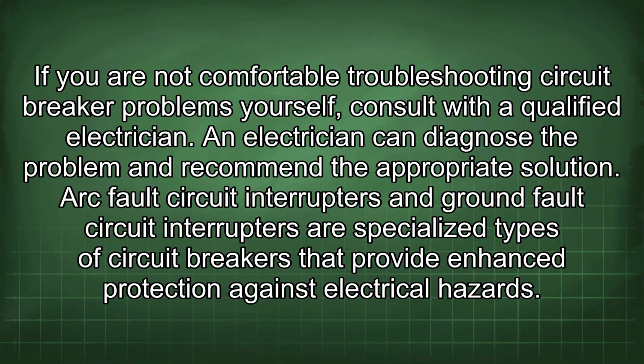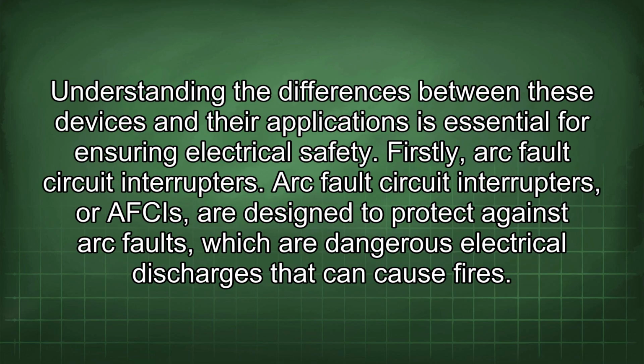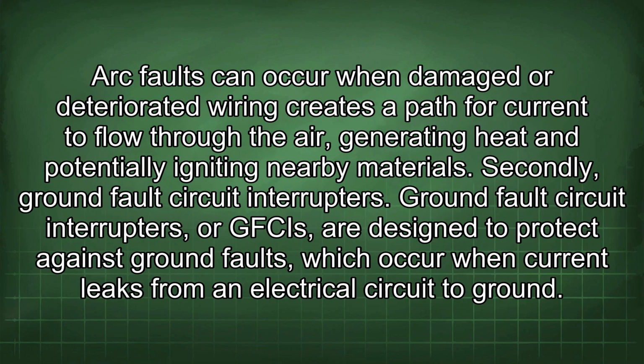Arc fault circuit interrupters and ground fault circuit interrupters are specialized types of circuit breakers that provide enhanced protection against electrical hazards. Understanding the differences between these devices and their applications is essential for ensuring electrical safety. Firstly, arc fault circuit interrupters. Arc fault circuit interrupters, or AFCIs, are designed to protect against arc faults, which are dangerous electrical discharges that can cause fires. Arc faults can occur when damaged or deteriorated wiring creates a path for current to flow through the air, generating heat and potentially igniting nearby materials.